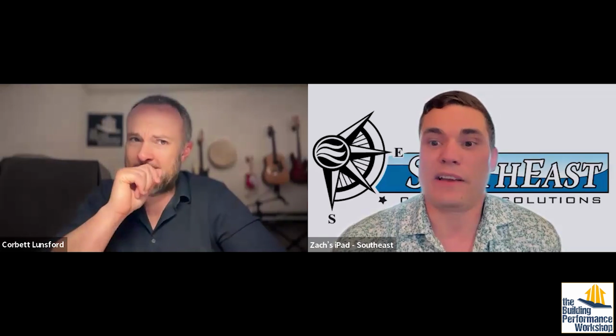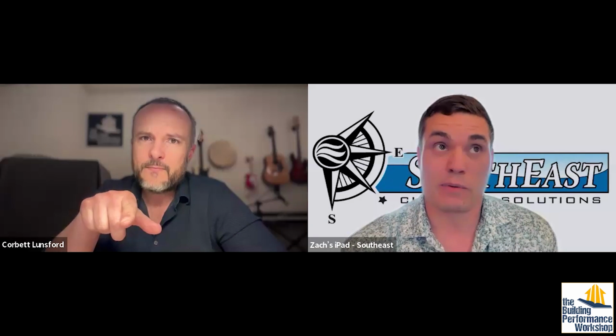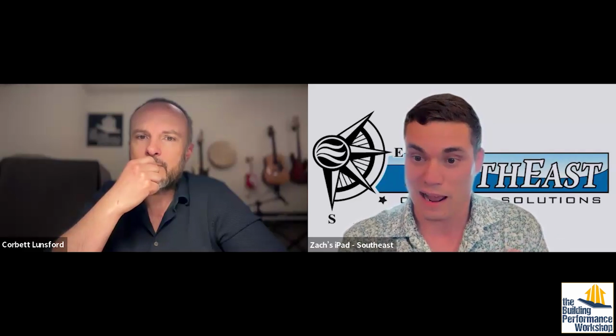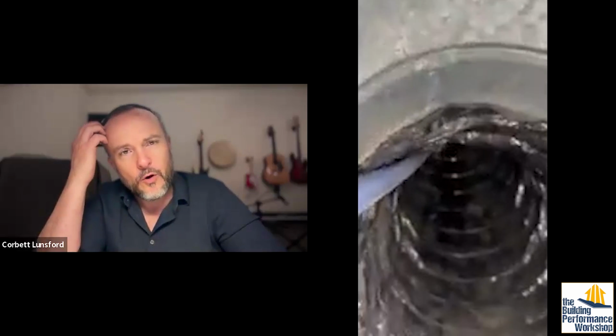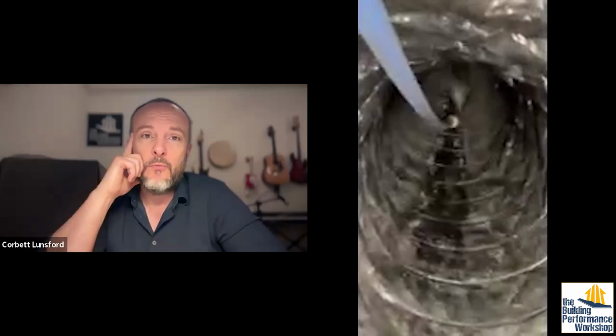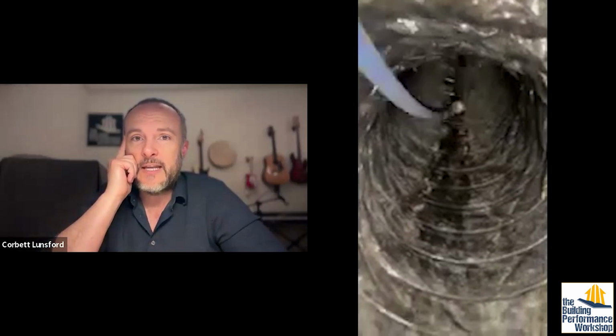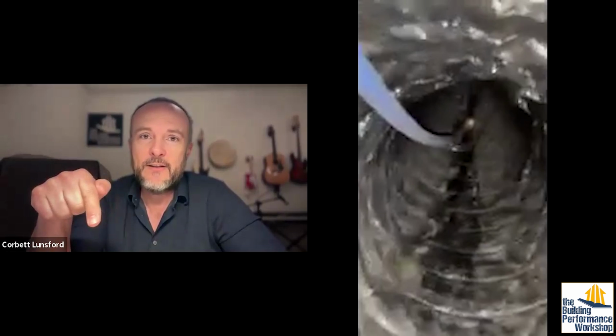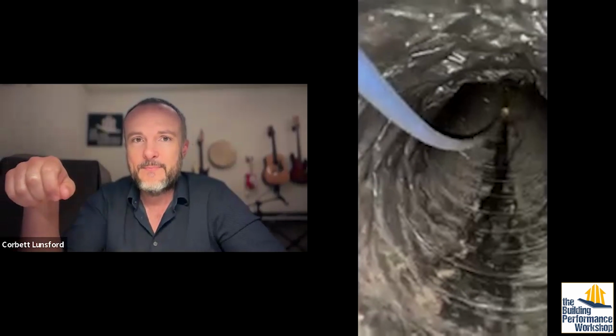If I were doing that with every single line, it might be more economical to replace it with new ductwork. Interesting. Yeah, and it seems like an attic, because it really will take, I mean, it could be north of 30 minutes to really get what's in that duct out. And are you worried about degrading this duct if it's older than 10 years old? Are you thinking that your process is going to actually degrade it?